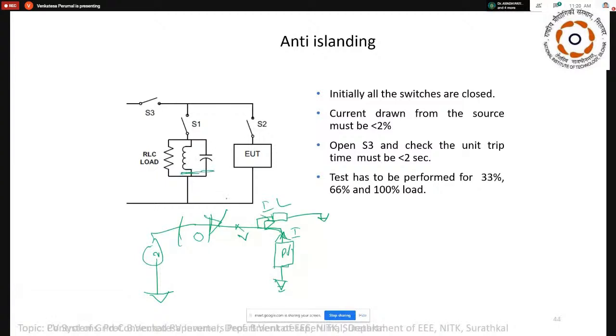If this circuit makes a tank circuit, the oscillation persists at 50 Hertz, which will not be noticed by your PV inverter, because at this point the voltage is sensed and given as an input to the system. So under this condition, the inverter thinks the grid is still there and that it can push the current. Then the person doing the maintenance work will get a shock. To avoid that, we need to check this condition. This is called anti-islanding. Once the system is islanded, we need to remove the inverter from the system itself.